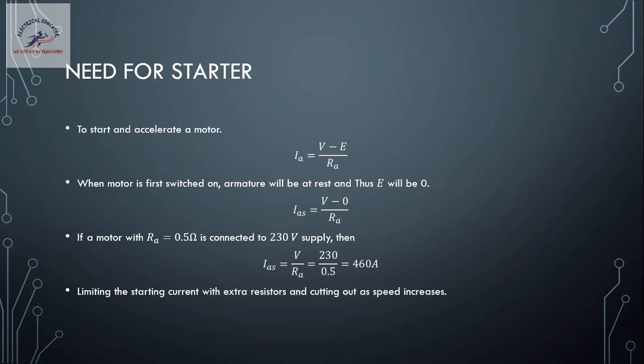Starters limit the starting current using extra resistors and cut them out as speed increases. One might ask: isn't this just the armature resistance control method? The difference is that the armature resistance control method adds a resistor in series throughout operation to vary speed. A starter, however, begins with the resistor at maximum and cuts it out progressively — the cutting-out technology and resistor design are also different.